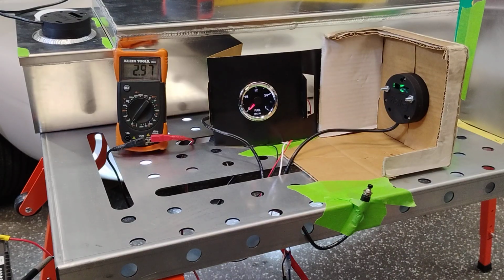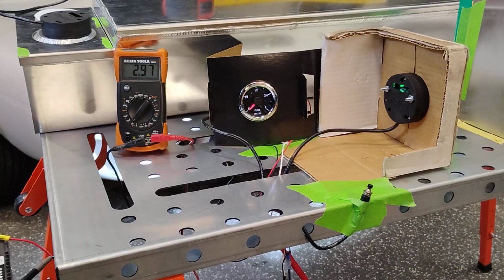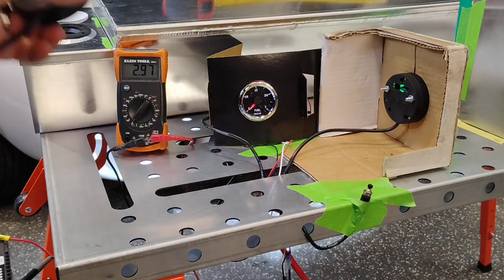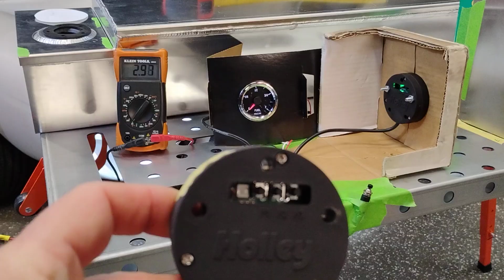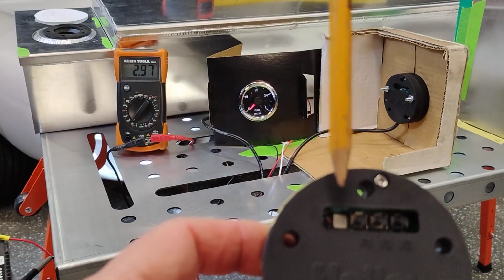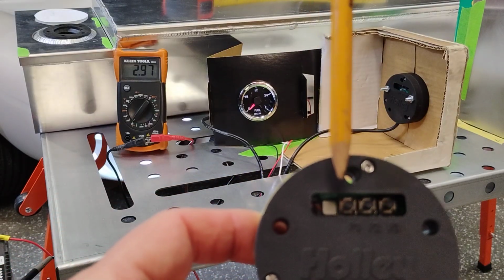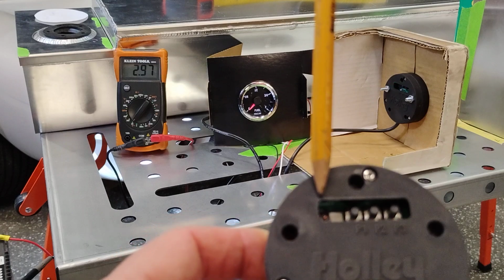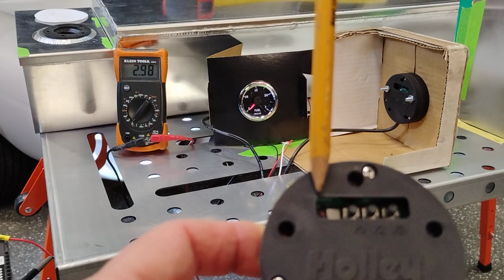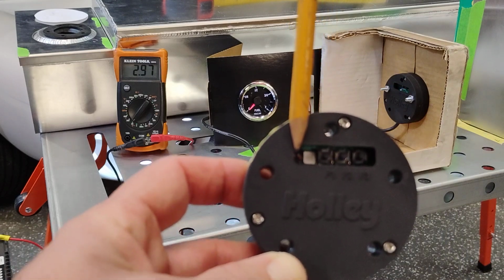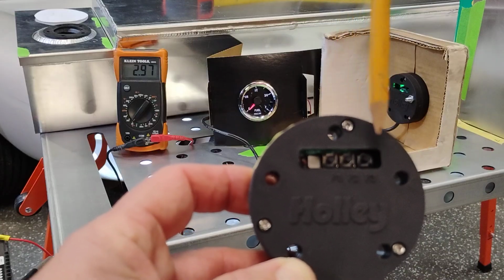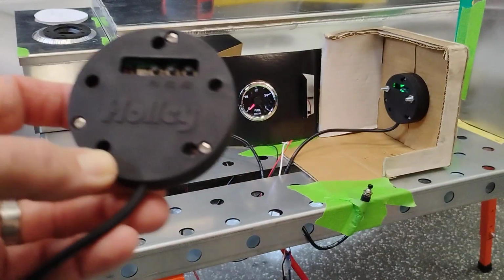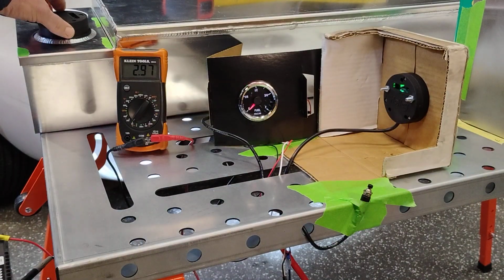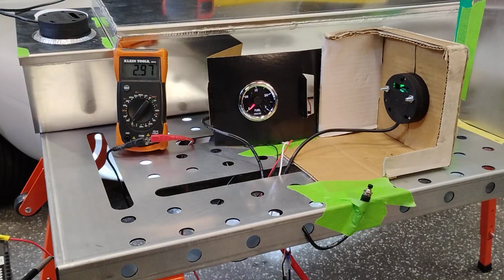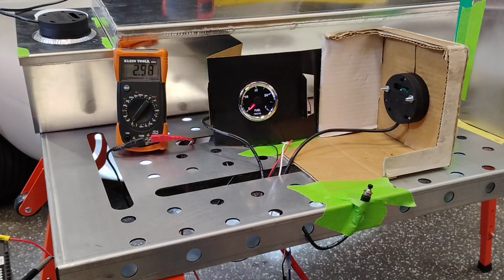But before you even start, take your sending unit, and you can see you've got a bunch of buttons and different settings on here. There are dip switches over here to the left. Set those up so that you are on the fastest response. And then, of course, you'll be using the P1, P2, and P3 buttons during the calibration sequences. So do yourself a favor and do that, so that as you go through the process and change the, quote, depth of the tank, things move quickly.